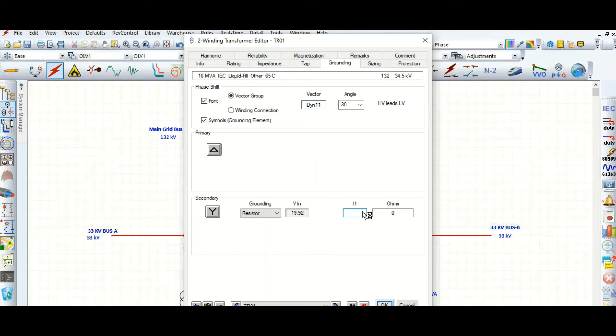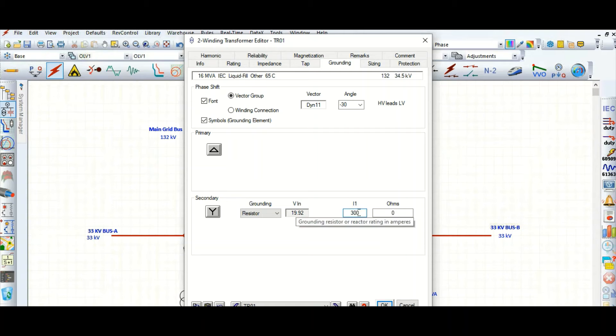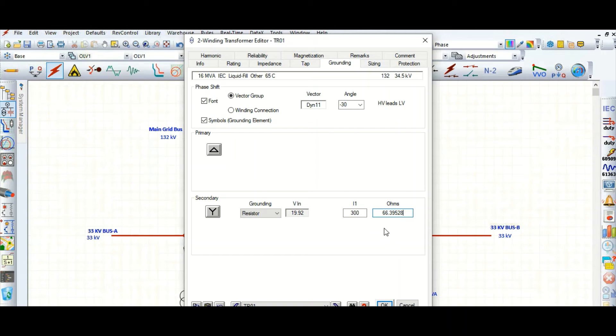Suppose I want to restrict the single line-to-ground fault to 300 amps. It will then calculate the NGR value — in this case 66.39 ohms. This is the value of the neutral grounding resistor.